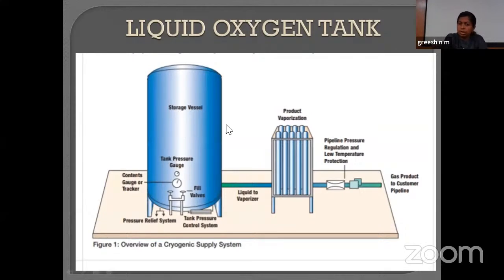If the cylinder is not used for several days, the pressure builds up extensively. And if this oxygen is used repeatedly, the pressure within the tank decreases. If the pressure in the tank decreases, there is a facility at the bottom of the tank so that the pressure of the liquid oxygen increases. So I want to say that this liquid oxygen tank has both mechanisms: one to decrease the oxygen pressure and the other to increase the liquid oxygen pressure.